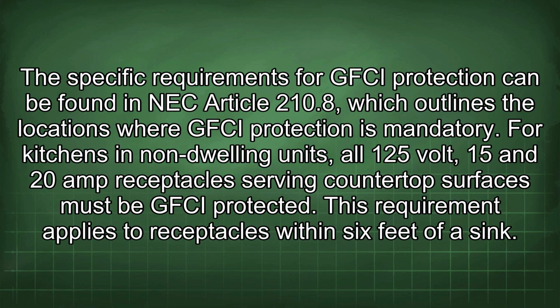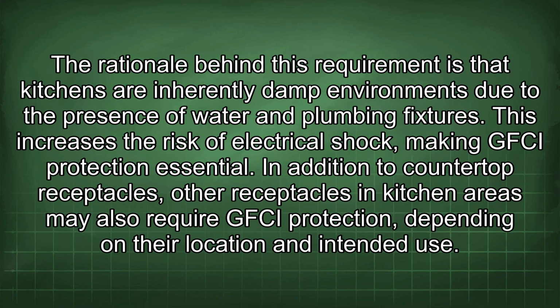The specific requirements for GFCI protection can be found in NEC Article 210.8, which outlines the locations where GFCI protection is mandatory. For kitchens in non-dwelling units, all 125-volt, 15 and 20 amp receptacles serving countertop surfaces must be GFCI protected. This requirement applies to receptacles within 6 feet of a sink. The rationale behind this requirement is that kitchens are inherently damp environments due to the presence of water and plumbing fixtures.